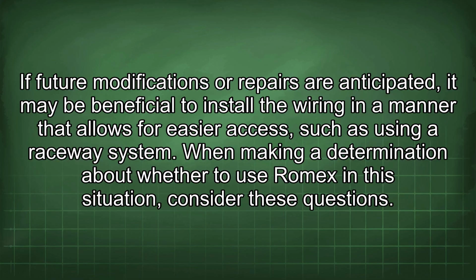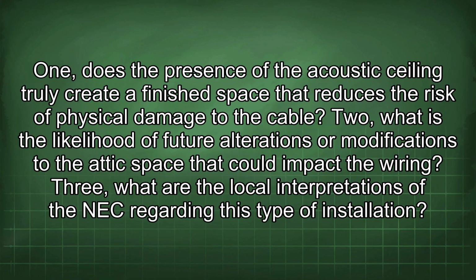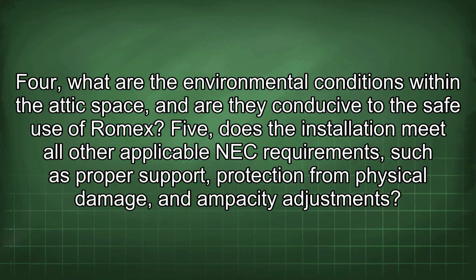When making a determination about whether to use Romex in this situation, consider these questions. 1. Does the presence of the acoustic ceiling truly create a finished space that reduces the risk of physical damage to the cable? 2. What is the likelihood of future alterations or modifications to the attic space that could impact the wiring? 3. What are the local interpretations of the NEC regarding this type of installation? 4. What are the environmental conditions within the attic space, and are they conducive to the safe use of Romex? 5. Does the installation meet all other applicable NEC requirements, such as proper support, protection from physical damage, and ampacity adjustments?